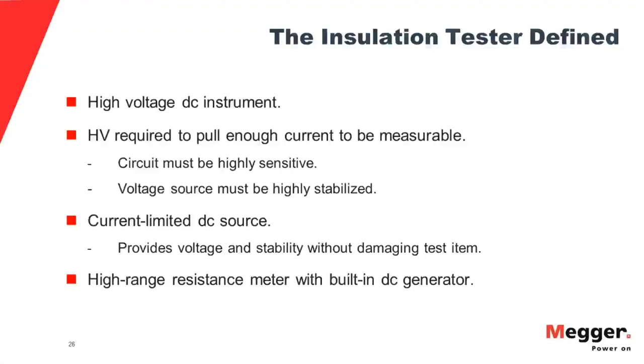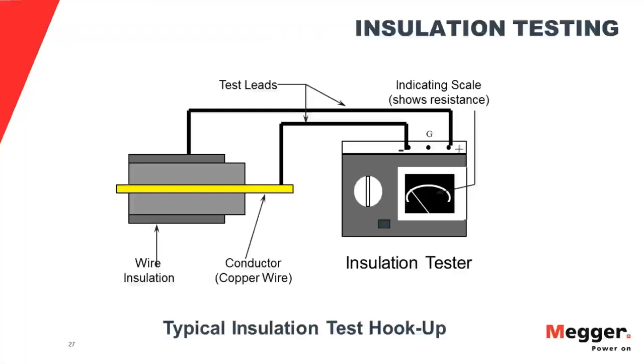There's a quick look at one. Two terminals, two leads, in this case going circuitry to ground. The positive terminal, that is not connected to the insulation. Every now and then I get a call of that nature. You do not ever connect to the insulation. You need two metal conductors. So that would represent, let's say, if you had a metal jacket on a cable, for instance, you could connect your positive terminal to that.